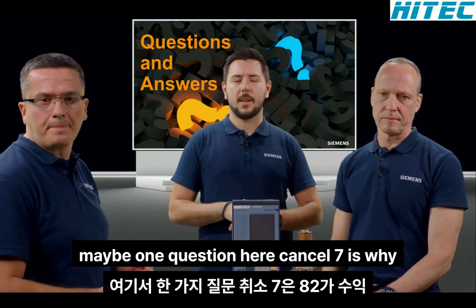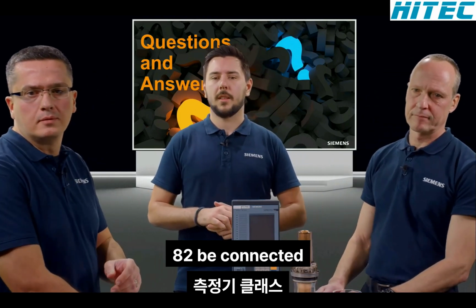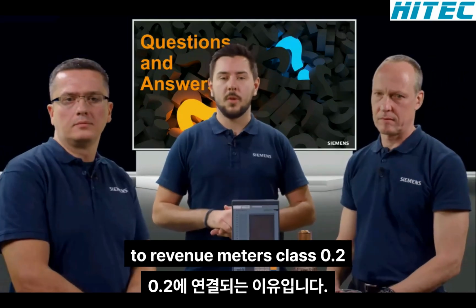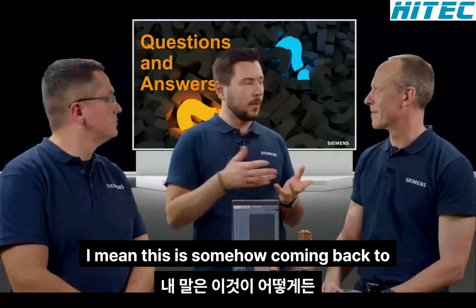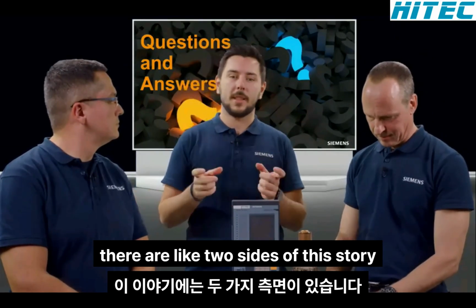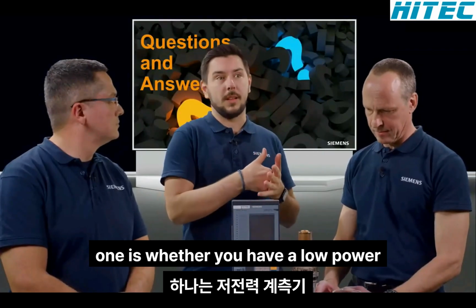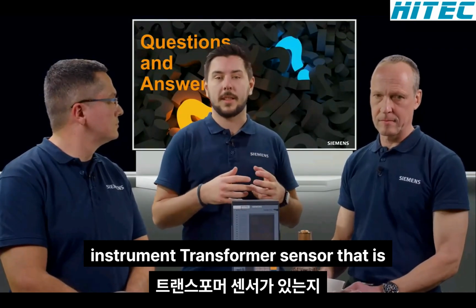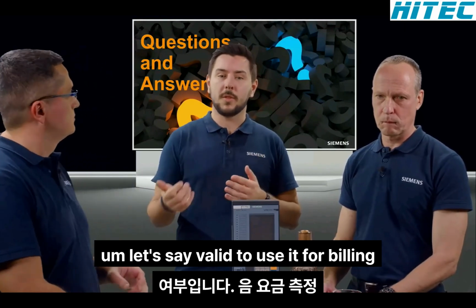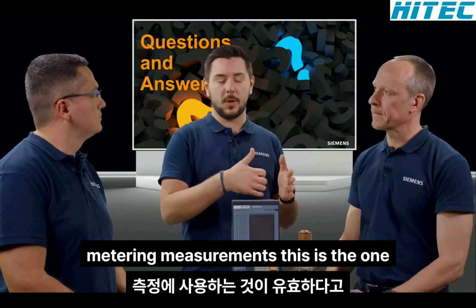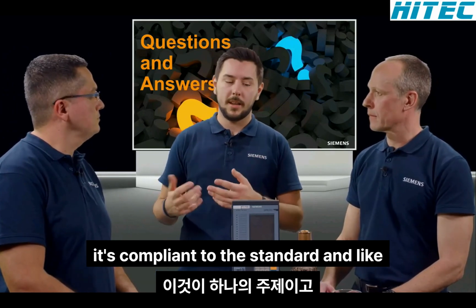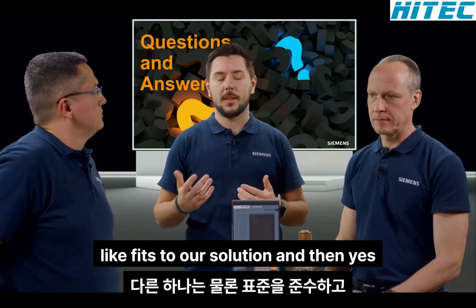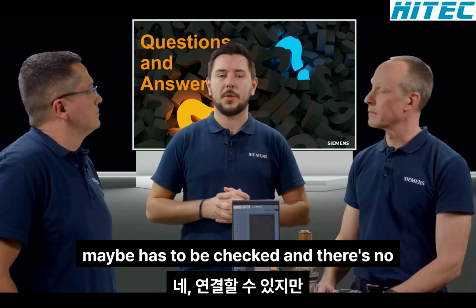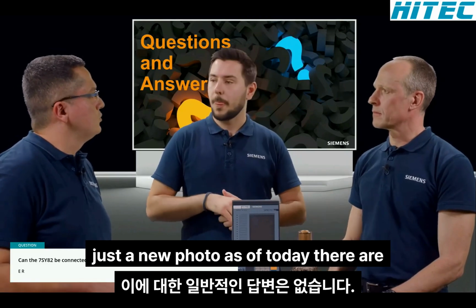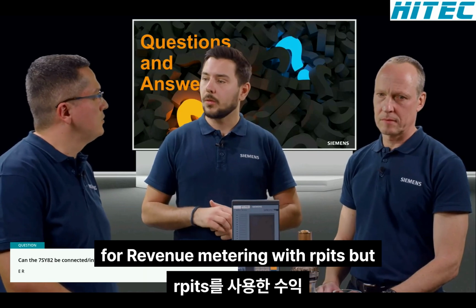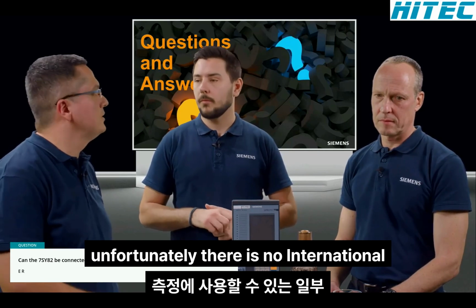So maybe one question here: can the 7SY82 be connected to revenue meters class 0.2? I mean, this is somehow coming back to the topic Bernd was just telling. There are like two sides of this story. One is whether you have a low power instrument transformer, a sensor, that is valid to use for billing metering measurements. This is the one topic. And the other one is, of course, if it's compliant to the standard and fits our solution, then yes, it's possible to connect it. But this maybe has to be checked, and there's no general answer for this. Just an info: as of today, there are even some national standards available for revenue metering with LPITs. But unfortunately, there is no international one.